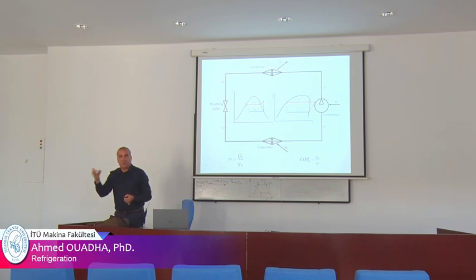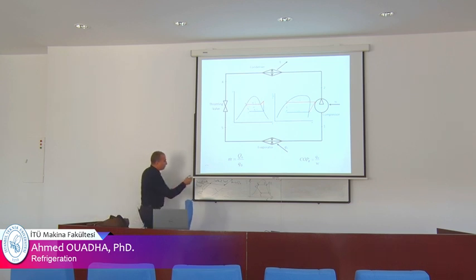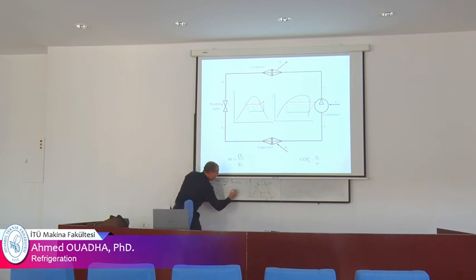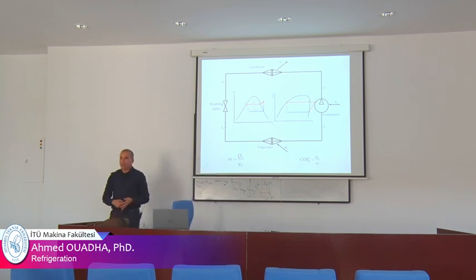12,000 BTU, 9,000 BTU, 18,000 BTU. This is the capacity. This is Q0, this parameter. Normally when we want to design a refrigeration system, we know three parameters. We know Q0, the refrigeration capacity, we know T evaporation, and we know T condensation. Three parameters. Is it clear? We know that.